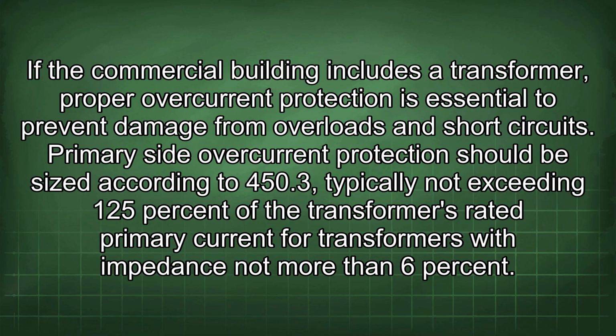If the commercial building includes a transformer, proper overcurrent protection is essential to prevent damage from overloads and short circuits. Primary side overcurrent protection should be sized according to 450.3, typically not exceeding 125% of the transformer's rated primary current for transformers with impedance not more than 6%.